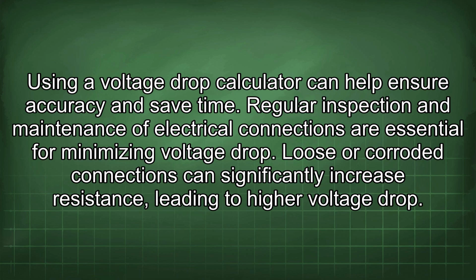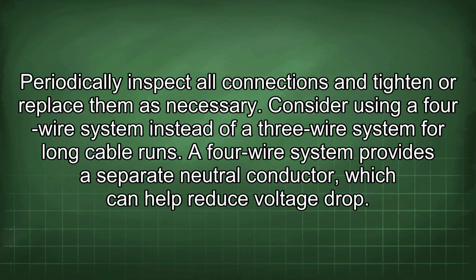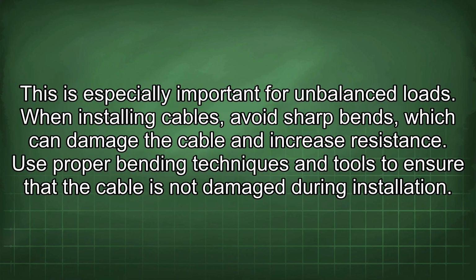Regular inspection and maintenance of electrical connections are essential for minimizing voltage drop. Loose or corroded connections can significantly increase resistance, leading to higher voltage drop. Periodically inspect all connections and tighten or replace them as necessary. Consider using a 4-wire system instead of a 3-wire system for long cable runs. A 4-wire system provides a separate neutral conductor, which can help reduce voltage drop. This is especially important for unbalanced loads. When installing cables, avoid sharp bends, which can damage the cable and increase resistance. Use proper bending techniques and tools to ensure that the cable is not damaged during installation.